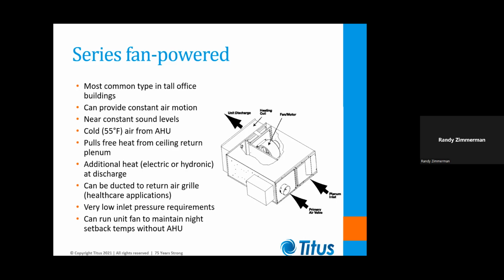And that leads to some funny phone calls that I take. You know, somebody will say, I think my blower's running backwards. And I'll say, what makes you think your blower's running backwards? And they go, well, we can't keep the filter on the induction port. And my next question is, why are you running the box with a filter on it? And then they say, well, it came with a filter, so we thought we had to keep putting filters on it. I said, well, the fact is most fan-powered boxes run without filters.